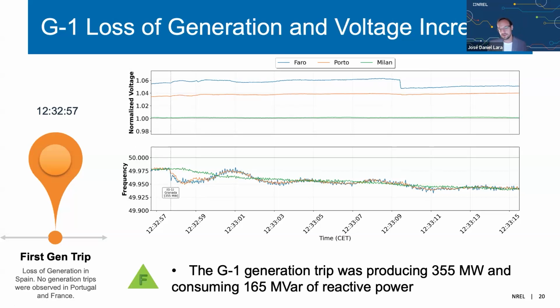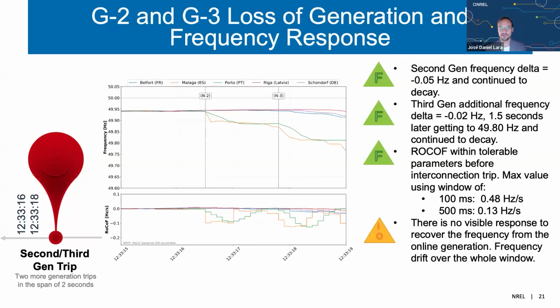The other part that becomes interesting in the context of voltage is that the report says very clearly that the very first one, generation 1, was a unit producing 355 megawatts, but it was consuming 165 MVAR of reactive power. So this is important because if you have an overvoltage problem already, and the plants that are tripping were actually consuming reactive power, providing regulation downwards of voltage, that just worsens your voltage problem.